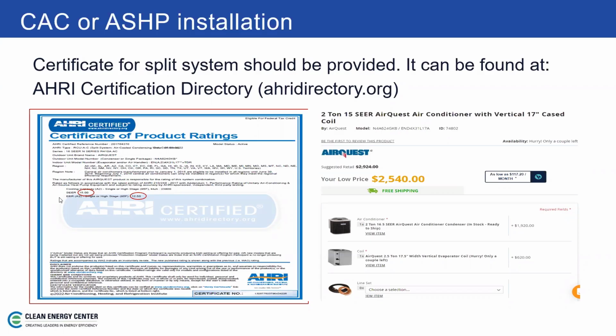SEER. So this is the AHRI certification we'd be looking for, and you can see this particular equipment match right here meets 15 SEER and 12.5 HSPF. So it is a good match. It's a single stage piece of equipment, so you don't need to worry about multi-stage equipment or anything like that. Whether or not you can actually get it if you ordered it, but this is what you're looking at for the indoor or outdoor condenser and the indoor evaporator coil, about $2,450.